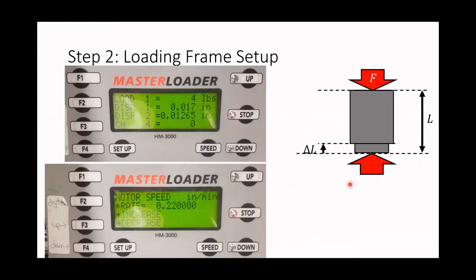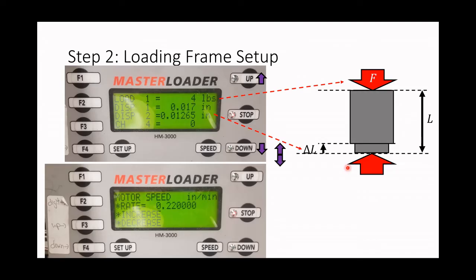To set the sample, we have to check the parameters used to handle the frame. When we operate the frame, we are moving the lower part. Based on that, we measure two main parameters: Channel one, which is the load we are applying in terms of force, and Channel three, which is the displacement — indicating the vertical displacement of the sample. We can choose to move the lower part either up or down to increase or decrease the force applied over the sample.